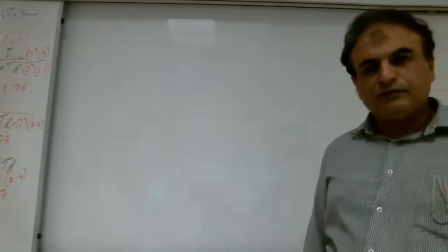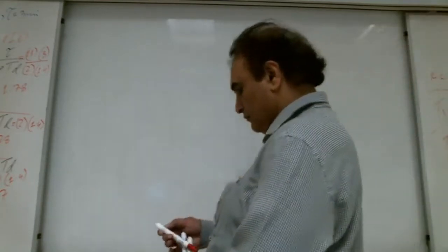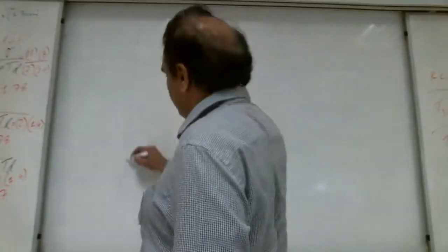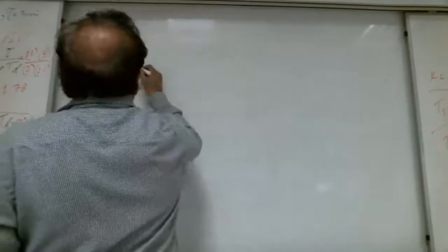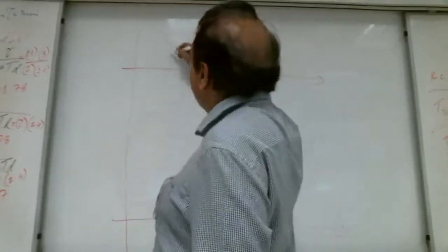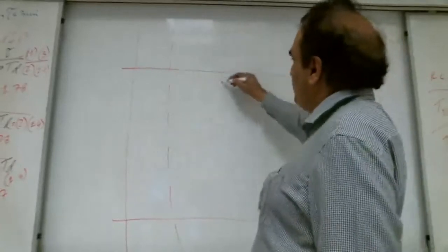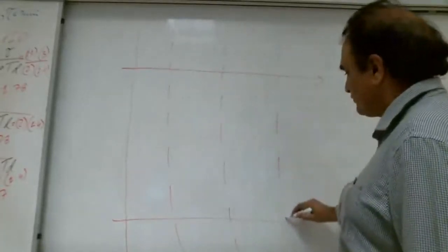Okay, Shabab, please read question 4.5. Calculate gain, integral time, and derivative time for the process reaction curve. Dead time is 10 minus 5, equal to 5 minutes. Okay, Shabab, this is given. What is given? Input is given and output is given like this.